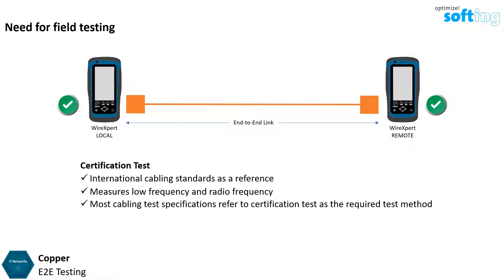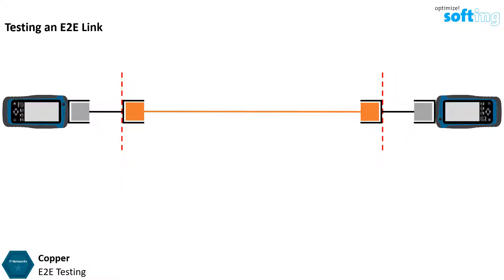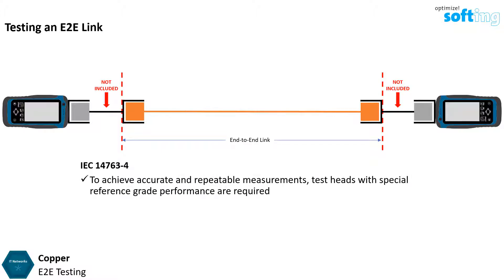Most cabling test specifications refer to certification test as the required test method. Since the ends of an end-to-end link can be terminated in the field, it must be ensured that both ends of the link are included in the measurement. The red dotted lines depict the reference plane, which delimits the part of the cabling included within the measurement. It is important that the testers and any measurement cables are not included, but the sockets at the end of the measurement cables are included. IEC 14763-4 specifies that to achieve accurate and repeatable measurements, test heads with special reference grade performance are required.